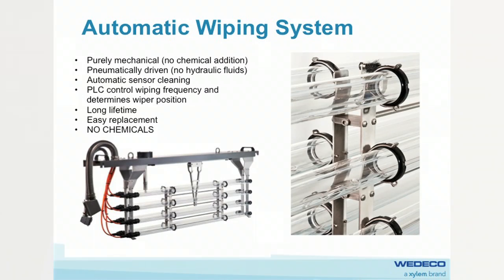It's all very well having a very good UV system, but if the UV light doesn't get into the water, you're not going to get the disinfection. Our systems come with purely mechanical wiping processes. It's a wiping sleeve which moves across the lamp on pre-regulated, or we have sensors that can pick up the changing in the intensity and wipe the system automatically.